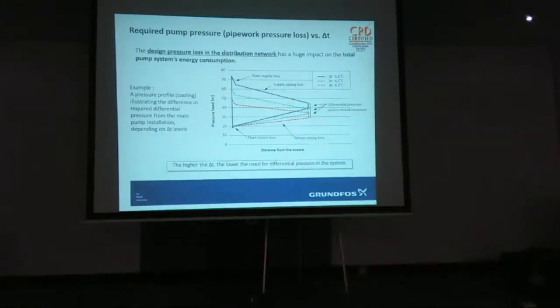It costs more money, but these things last 25 years or more, in district energy still could be even 40 years. So you're talking about an arm and a leg to run some of these schemes. So basically, the higher the delta T, the lower the need for differential pressure in the system. So buildings on the early part of the circuit are seeing a higher rise or fall in pressure as you go down the circuit. If you've got less losses, you've got a smaller pressure differential as you go down the street. Do you disagree or agree with that?